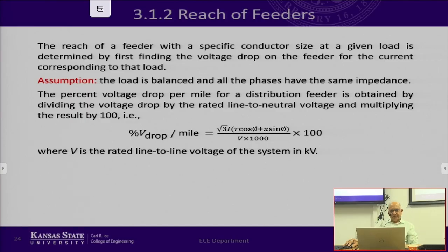So this voltage is line to line voltage, and that has to be divided by square root of 3 to get the line to neutral voltage, so the square root of 3 goes up there. And 1000 is because the upper equation is in volts and the lower one is in kilovolts, so you convert that to volts and then multiply by 100. So this gives you voltage drop per mile.